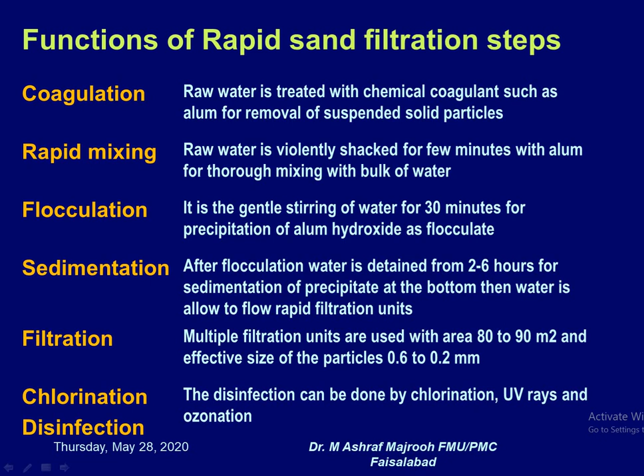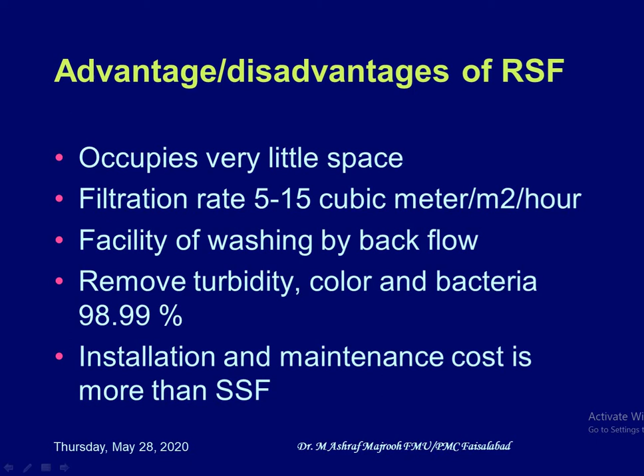The advantage and disadvantage of rapid sand filtration: it occupies very little space as compared to slow sand filtration. Filtration rate is 5 to 15 cubic meter per meter square per hour. The facility of washing by backflow is there as compared to scrubbing in the slow sand filtration. Removal of turbidity, color and bacteria is 98.99%. The installation and maintenance cost is more than the slow sand filtration. So this is the large scale purification. These are the large scale purification methods.